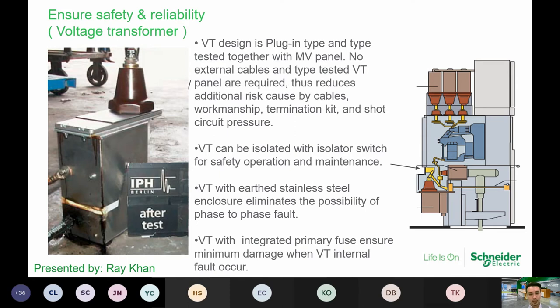All right, so this actually reduces a lot of risk in terms of the workmanship and also in terms of the termination. All right, so the VT can also be isolated using an isolating switch for safety operation and also for maintenance. So that in a way, the switchgear together with the VTs being fully delivered to the client in terms of warranty issues is also well covered as well.